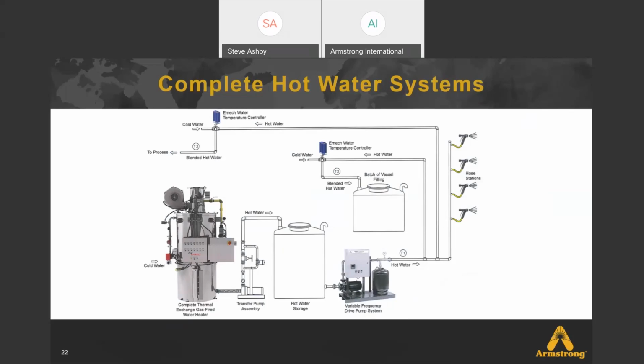There's level control in the storage tank, and as that level drops to a certain point, it starts the heater, and then the heater just runs for 10 to 15 minutes and fills that tank. So the tanks are sized to go along with the heaters themselves. Since this is an atmospheric system, then coupled to the tanks is a booster pump that's always required to move the water to the points of use.